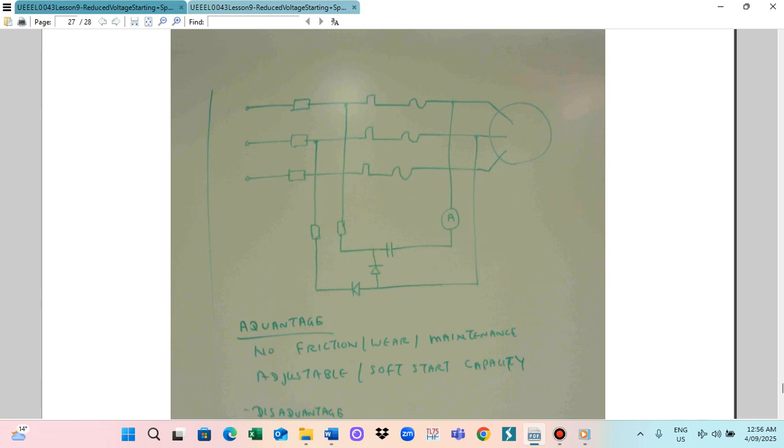At that time we ran the motor, a very big DC motor, and what happened is the motor became very hot. So we went and checked everything. All the electrical connections were correct, nothing wrong. Normally when a motor is hot, you think the motor is burning and you get some smoke. But the motor was good, nothing wrong with the motor.